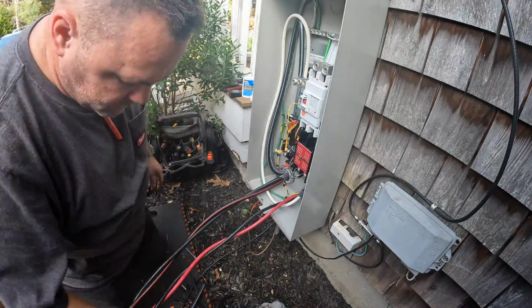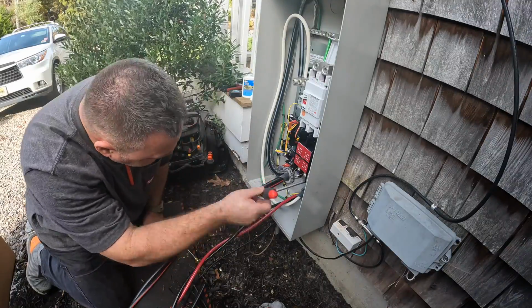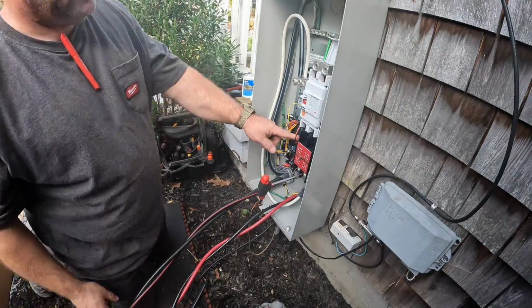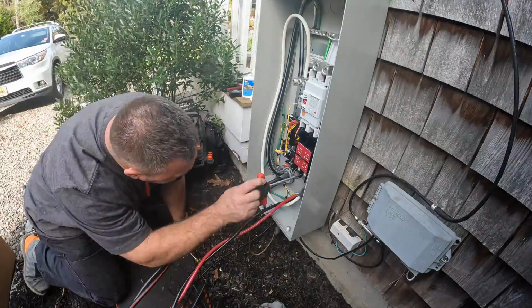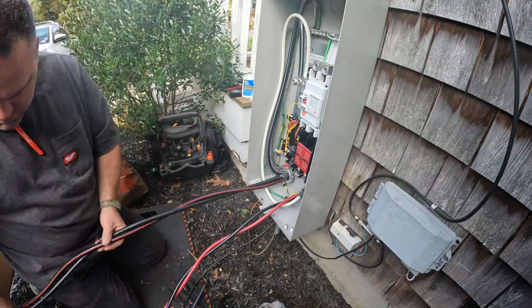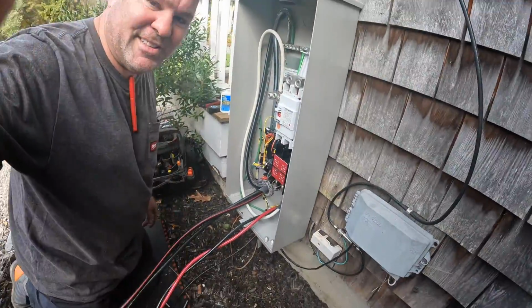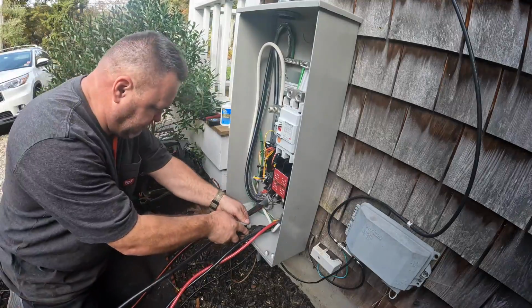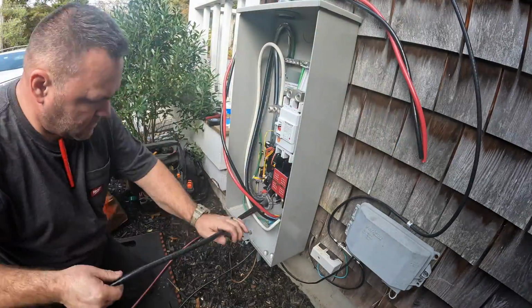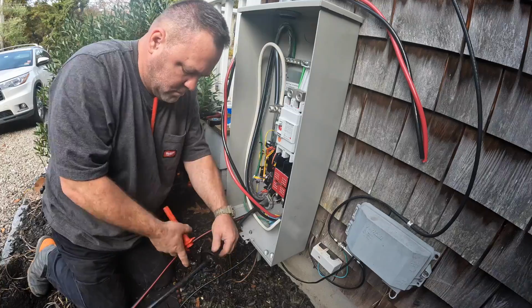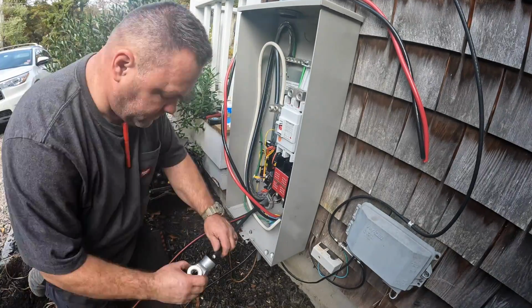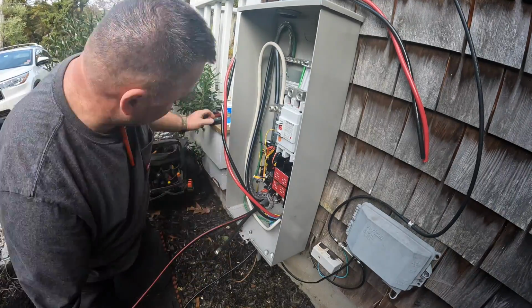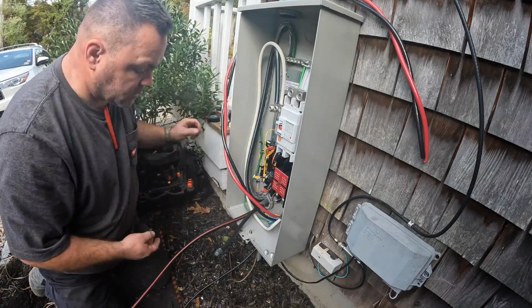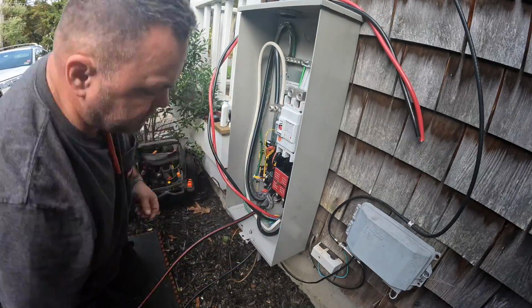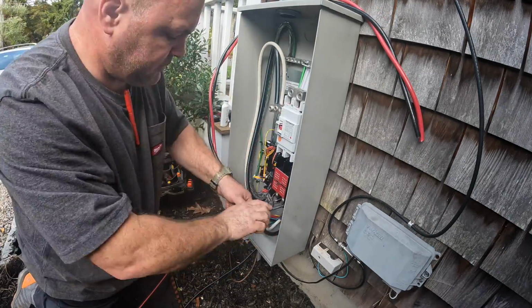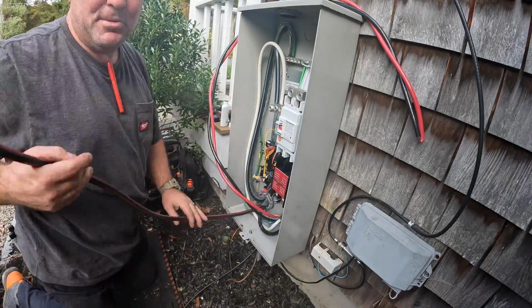So as you can see, I have the neutrals and grounds terminated, and now I'm going to start terminating the, I think the T1 and T2, which would be the panel conductors first, and then I'll terminate the generator conductors second, so that the conductors aren't in the way when you're terminating. That's why we do that. Also, I'm making sure I use plenty of Penetrox here, even though it's not required, because I believe it's a good product to protect your aluminum conductors.